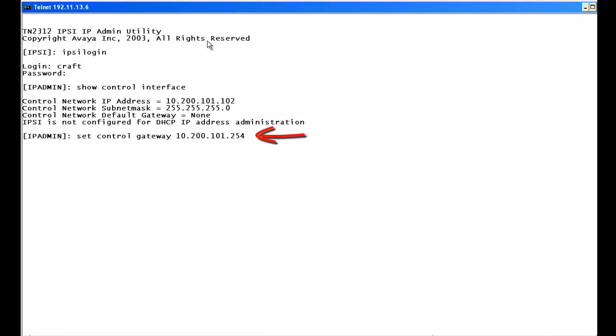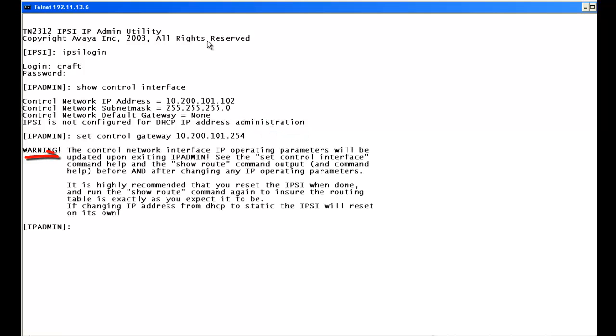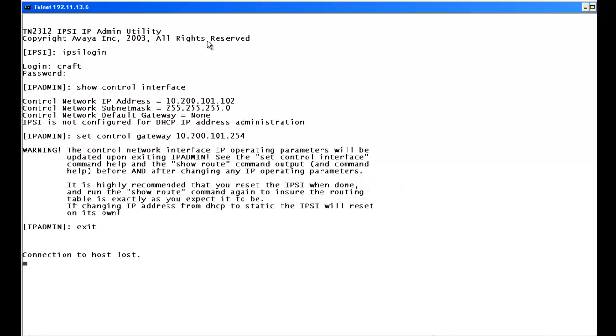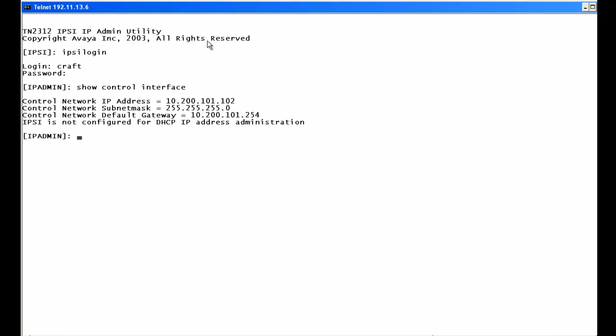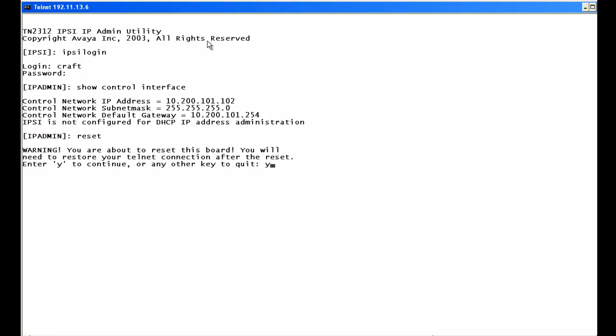We type set control gateway followed by the IP address of our router. The same rules apply — you must exit upon completion for the setting to take, then reset when done. We exit, connection is lost, and we telnet back into the board. Logging in with craft credentials, we run show control interface to check. The default gateway is now set. However, just like the IP address, we must reset for it to fully take effect. We type reset and confirm yes.